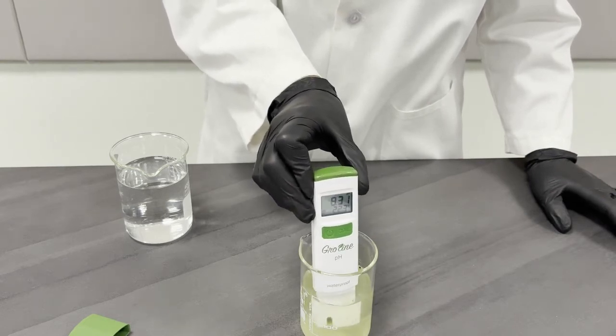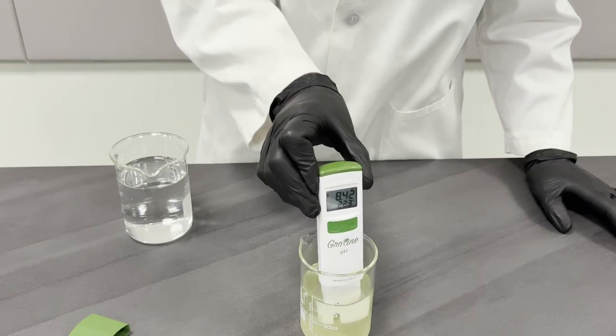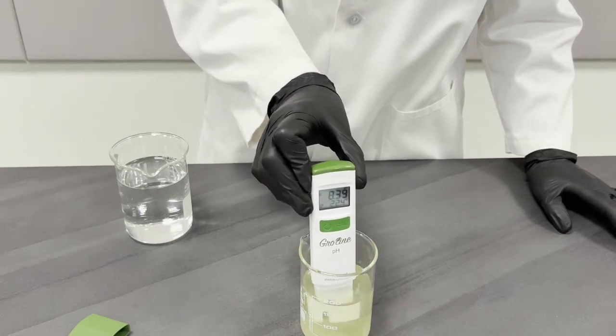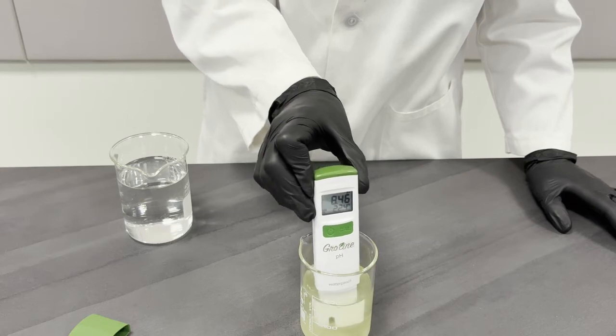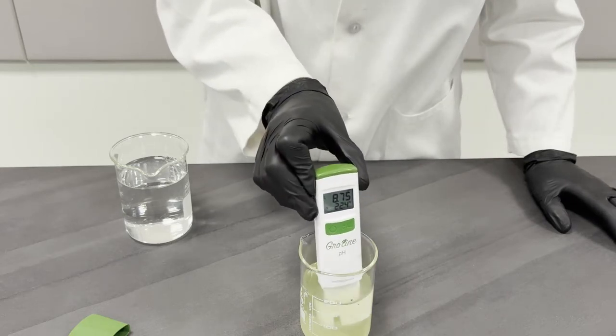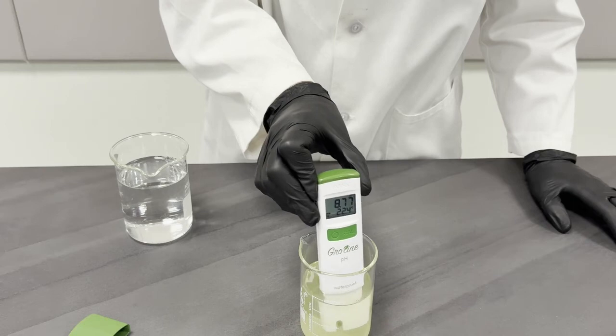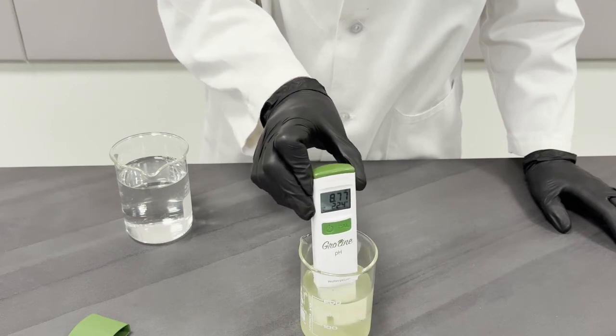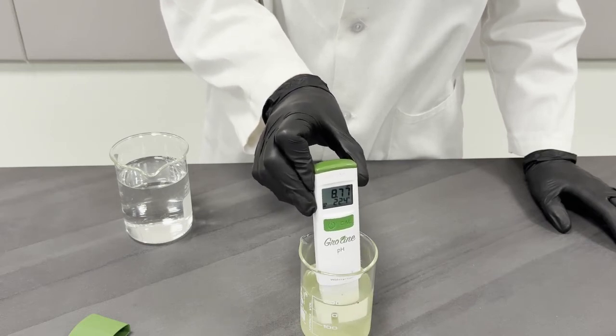Do this until the meter's stability indicator, or the small hourglass symbol on the top left, stops flashing on and off, and the value displayed in bigger numbers at the top of the display stops changing. Keep the meter submerged and record the value displayed.